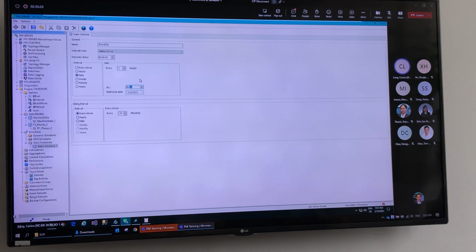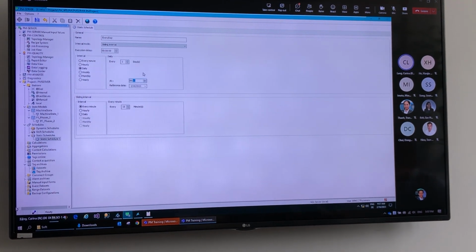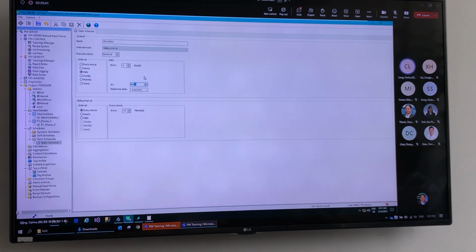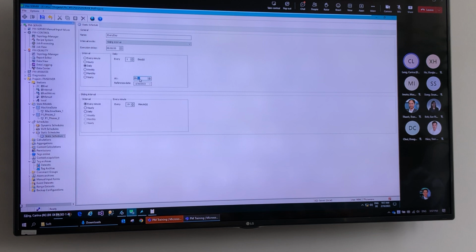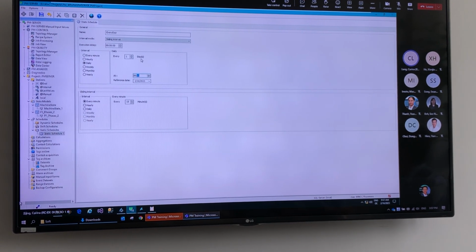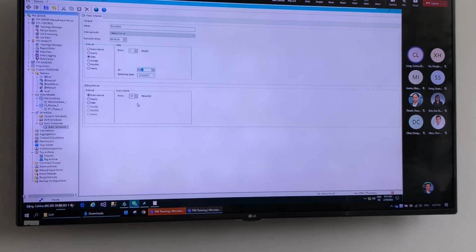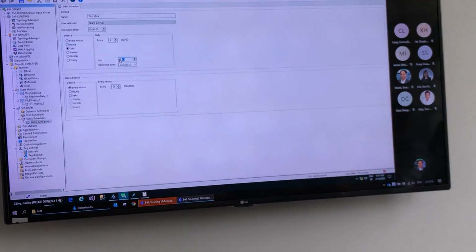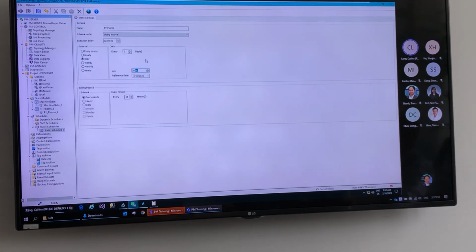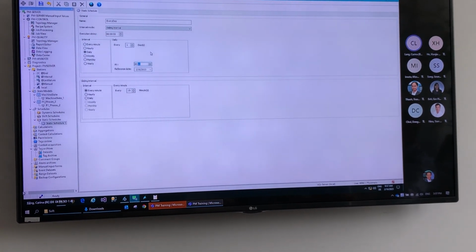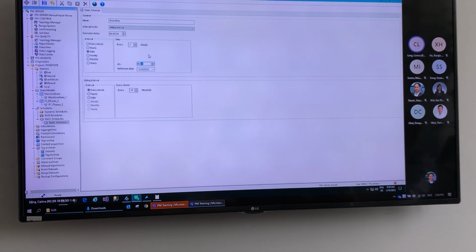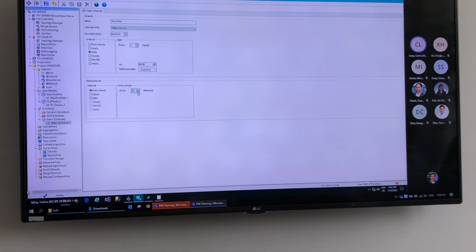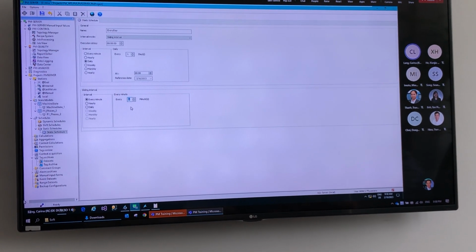And using the intermediate values or the sliding interval, we're just increasing the time range for the calculation there. So we start at 9 a.m. and 53 minutes in this case. Of course, we can change them to midnight, for example. And then we receive every 15 minutes an intermediate value for this point of time. Right, so we will change that to midnight so that we receive the value for a complete day. And we will change that one here to 1 minute. So we will go down to 1 minute so that we do not have to wait.